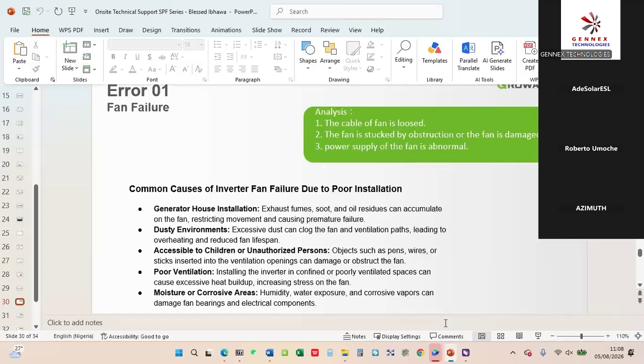For example, error 1, which talks about fan failure: a lot of things can cause this. Most times it's due to the installation environment, maybe you installed the inverter in a generator house, a dusty environment, accessible to children or unauthorized persons, poor ventilation, or installed in a moist area, for example near a beach. If you install your inverters in such beach areas, over time the fan will be picking up vapor and the components will rust. So please try to get a very good installation point for the machine.